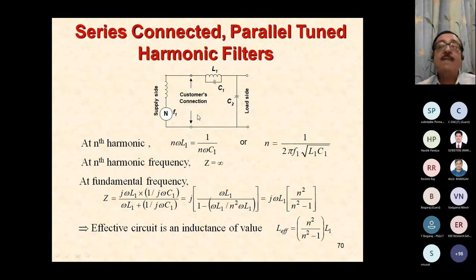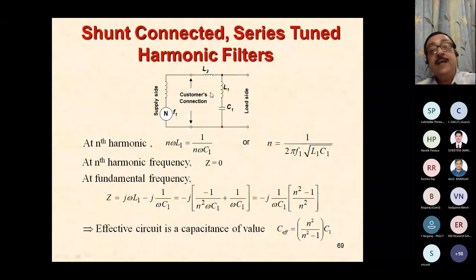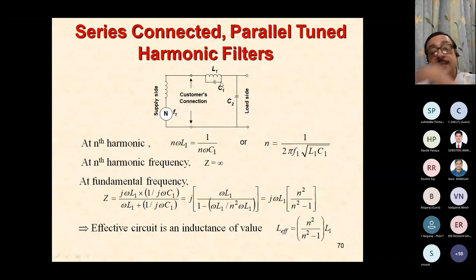You can also have series connected parallel tuned harmonic filters. If you have a parallel tuned LC at the nth harmonic, then the impedance becomes infinite, which means the harmonic is not permitted to flow through it. That is good in another alternative way, but the problem is that the entire load current has to be carried by this filter, which was not the case in the earlier system, because only the harmonic current was carried by the filter. So therefore, most of the time we prefer the shunt connected filter rather than the series connected filter.